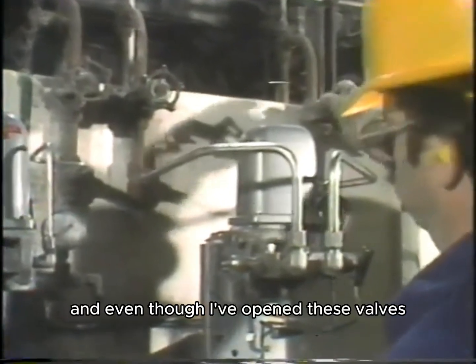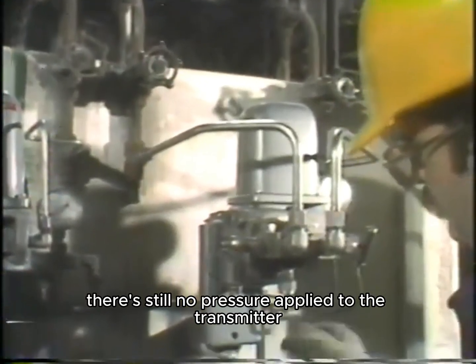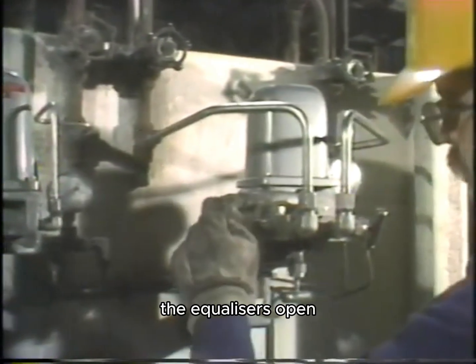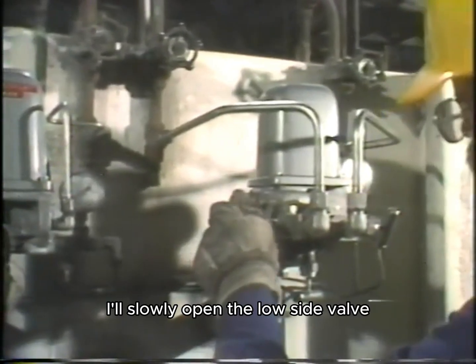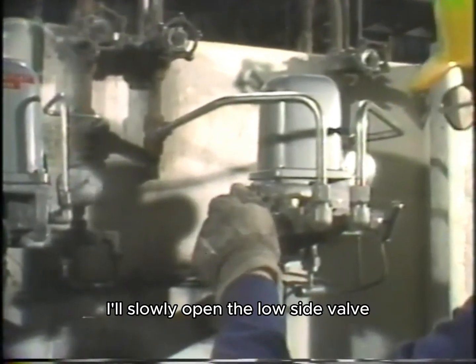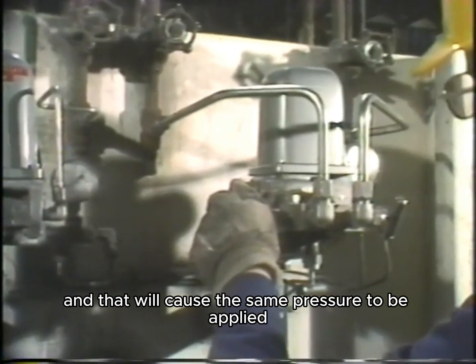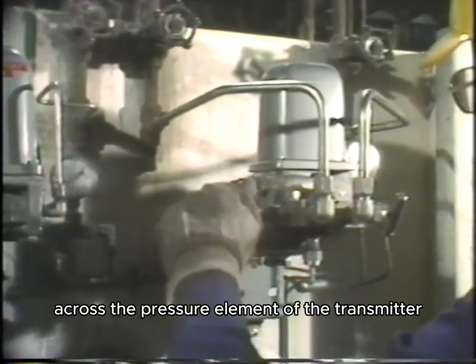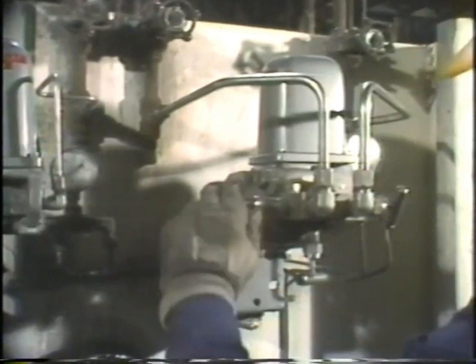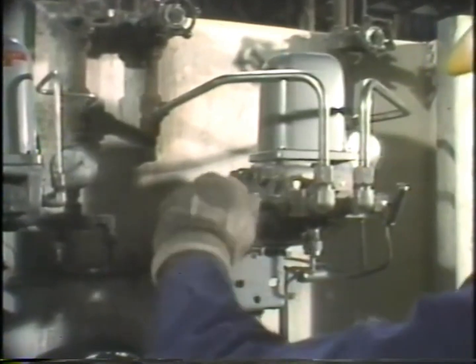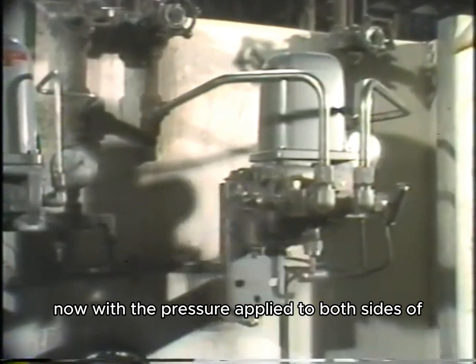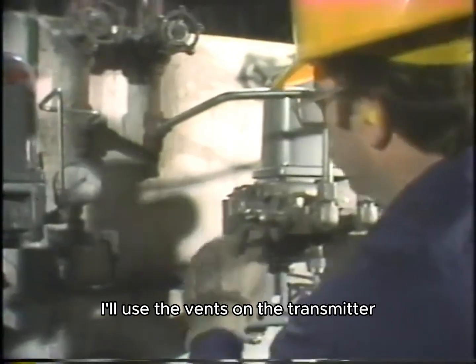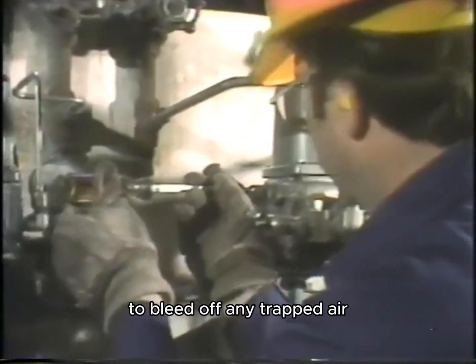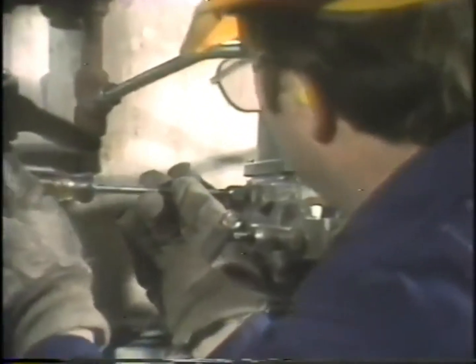Even though I've opened these valves, there's still no pressure applied to the transmitter. The equalizer's open. I'll slowly open the low side valve, and that will cause the same pressure to be applied across the pressure element of the transmitter. Now, with the pressure applied to both sides of the pressure element, I'll use the vents on the transmitter to bleed off any trapped air.